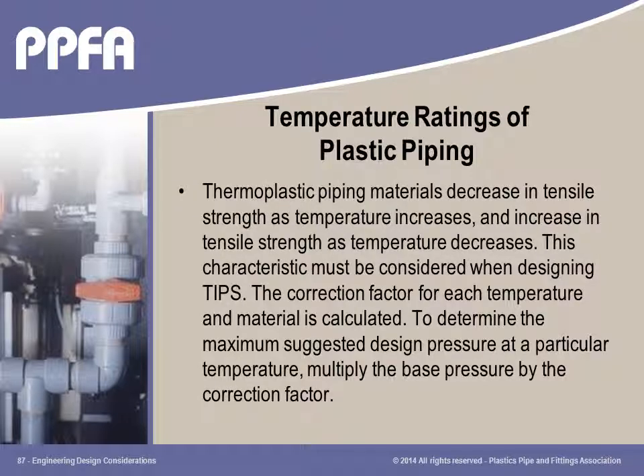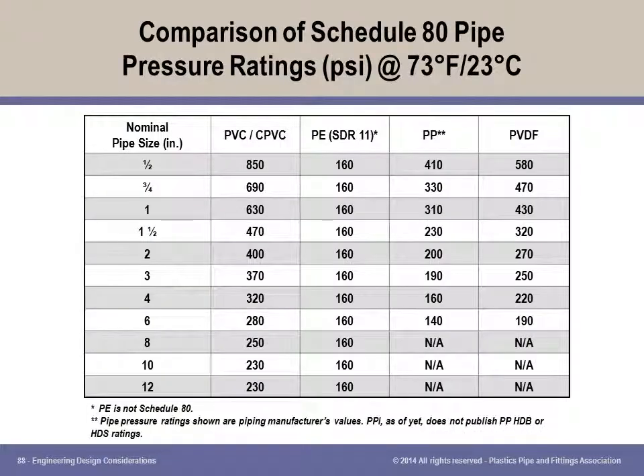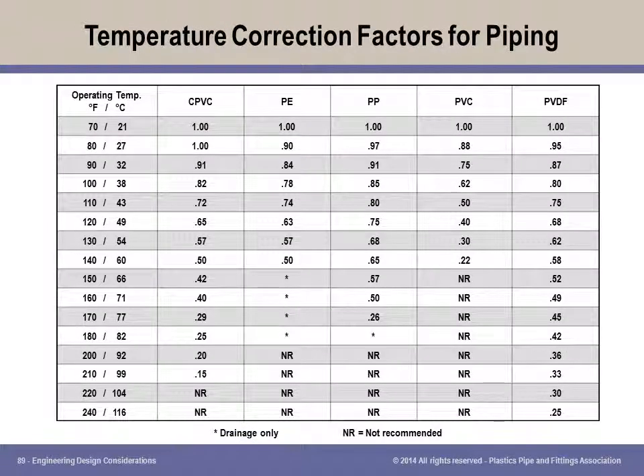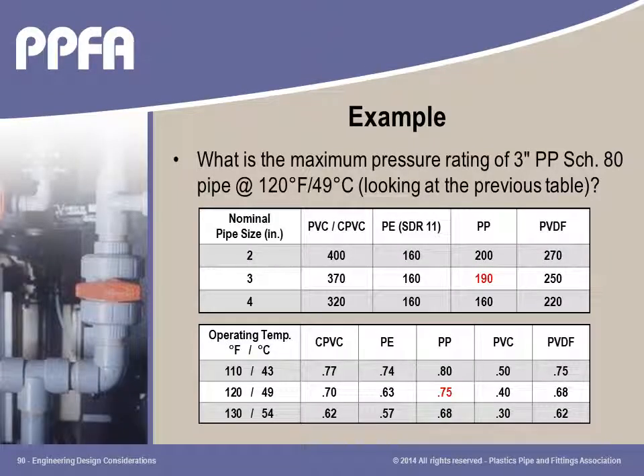Knowing the relationship of the temperature and pressure of the fluids being transported by thermoplastic piping is critical for a successful installation. The rule in thermoplastic piping is, as the operating temperature of a fluid increases, pressure rating of the thermoplastic pipe decreases. The working pressure of Schedule 40 and 80 thermoplastic piping mostly decreases as the pipe diameter size increases. Temperature correction factors for derating the working pressure of thermoplastic piping are available from the manufacturer. In the example shown using manufacturer-published tables, it is easy to determine the maximum pressure rating for any application.